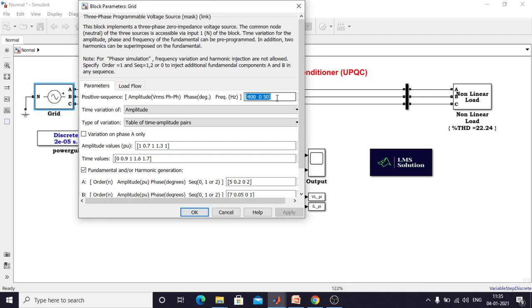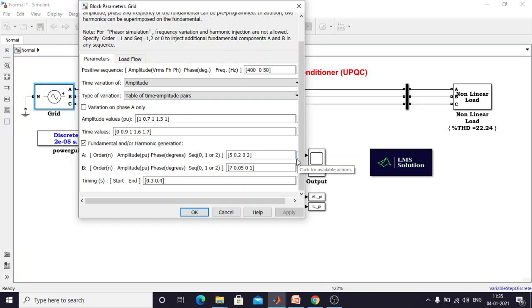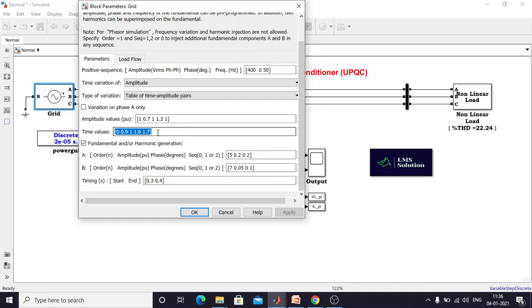I am going to use a line-to-line amplitude equal to 400. The frequency is 50 Hz. I am going to create a voltage disturbance scenario and harmonic disturbance scenario — that means voltage sag and voltage swell. The amplitude of the input source voltage varies as 1 per unit, 0.7 per unit, 1, 1.3, and 1. The timing for that amplitude variation is 0 to 0.9, 1, 1.6, and 1.7 seconds, which is used for creating voltage sag and swell.